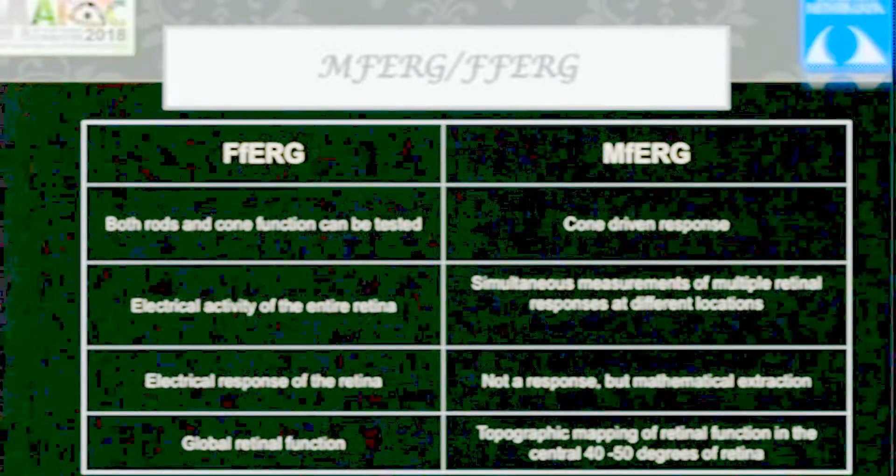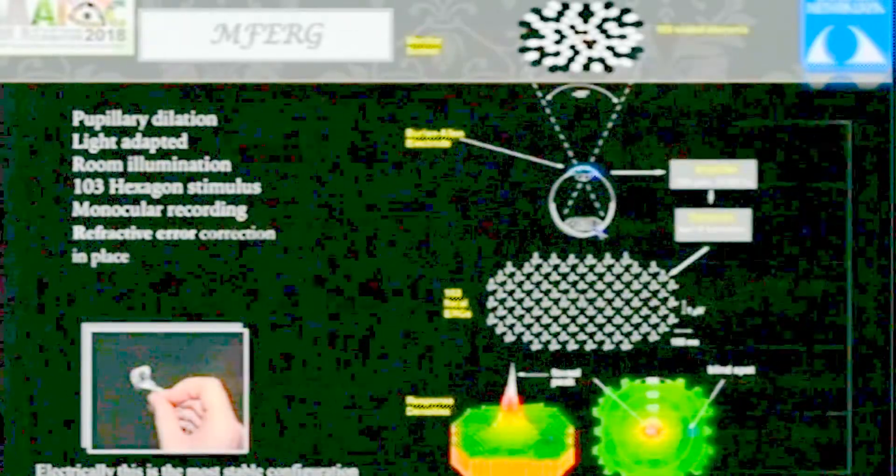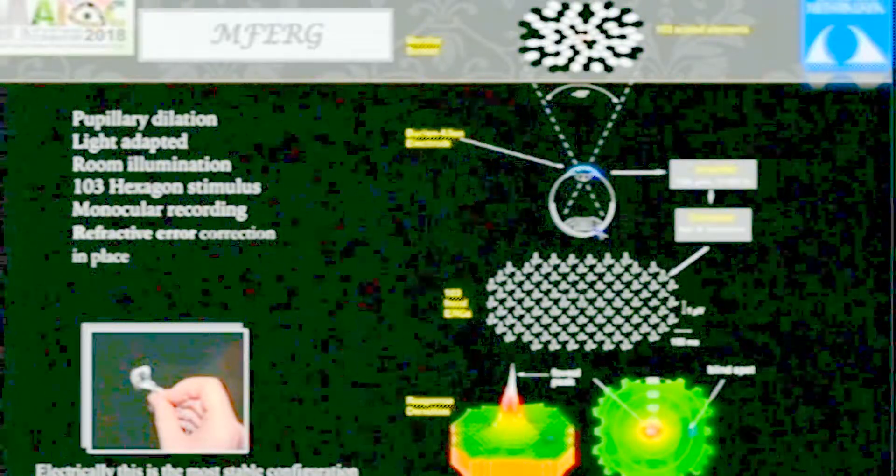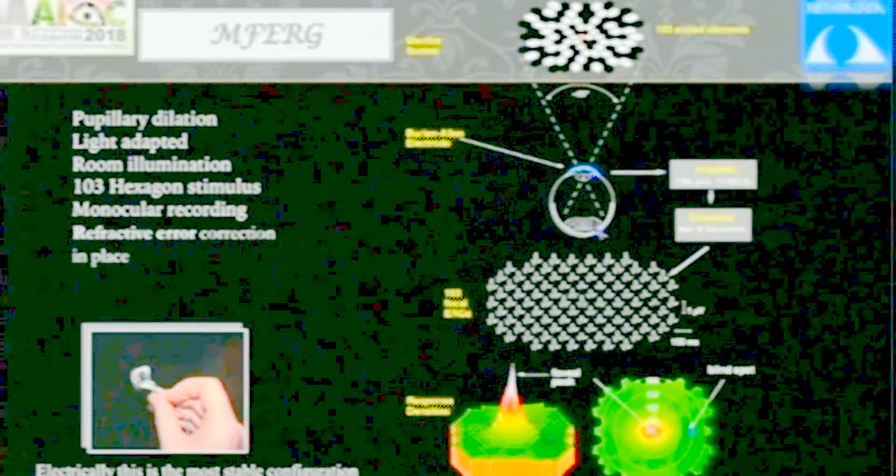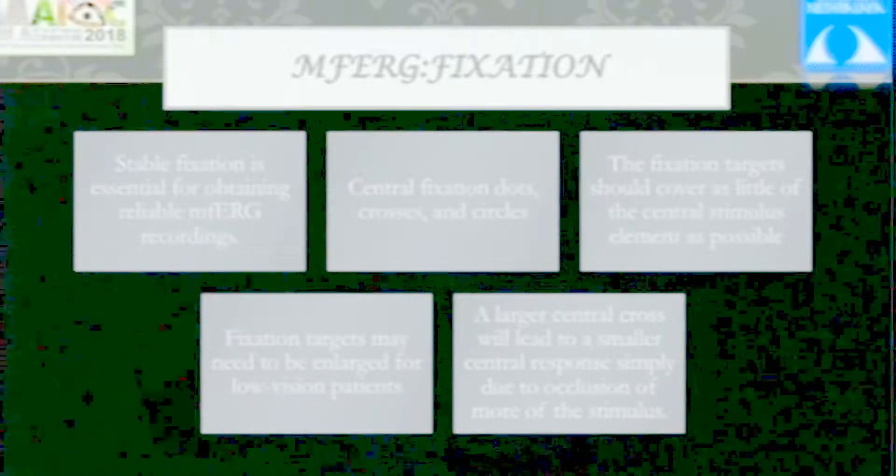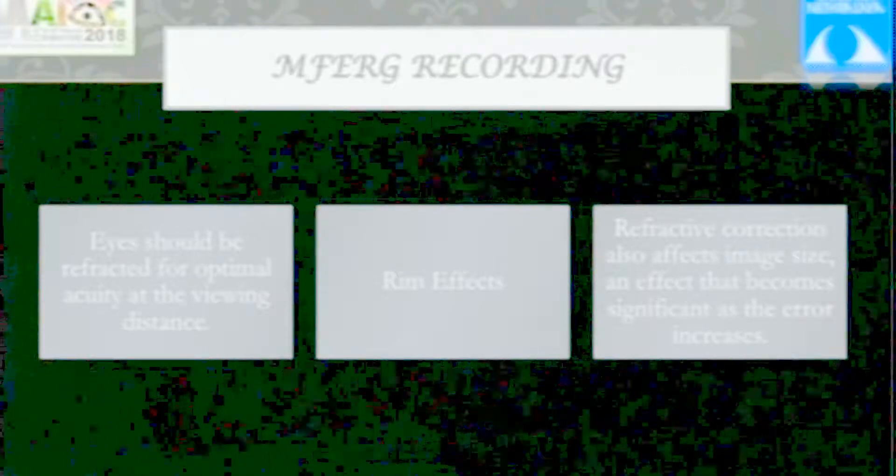Since we're recording multifocal ERG always in light-adapted conditions, the responses are cone responses - rod responses are not measured. Recording should be done with pupillary dilation under light-adapted conditions with normal room illumination, monocular recording, and refractive error correction in place. Fixation is very important because you're measuring the central 40 to 50 degrees, and these responses will differ if fixation is not proper. Eyes should be refracted, but be careful about peripheral rim effects from spectacles.